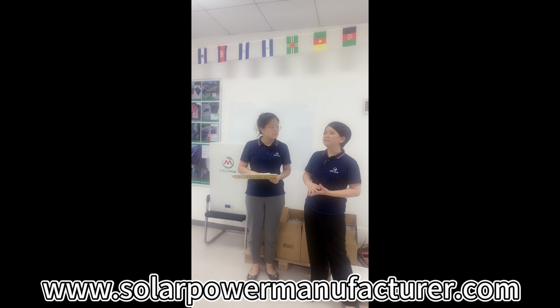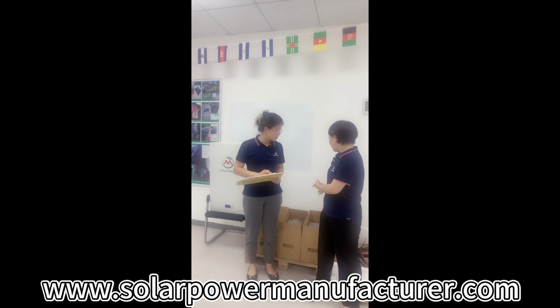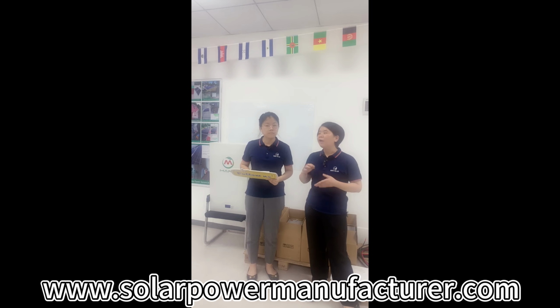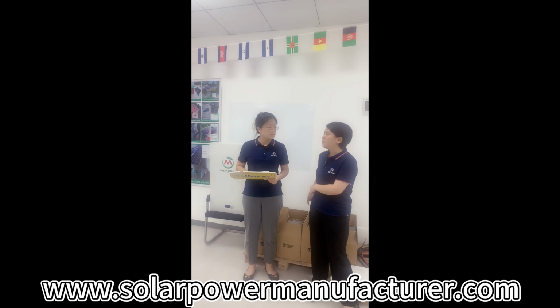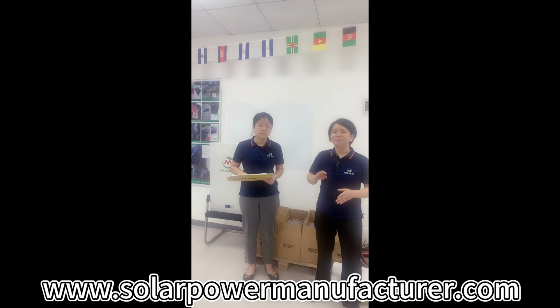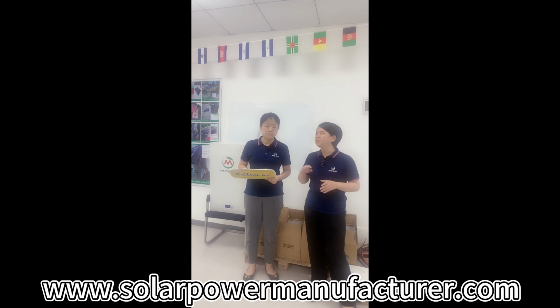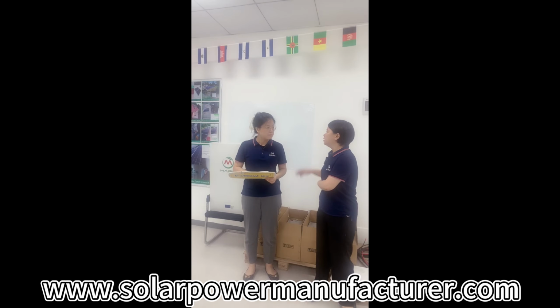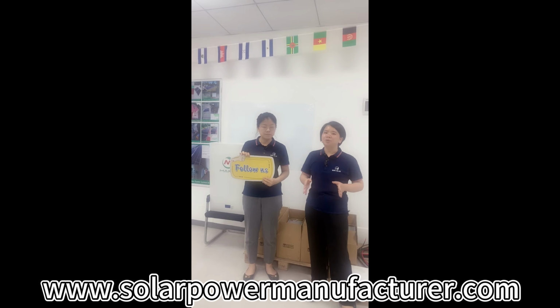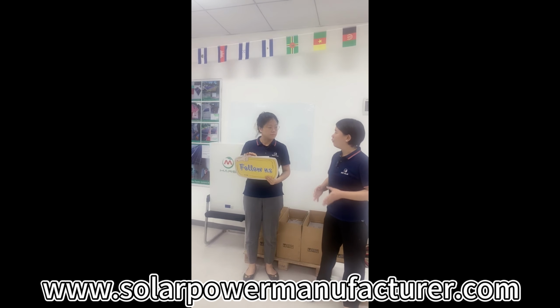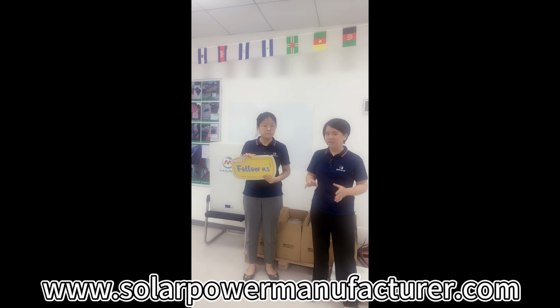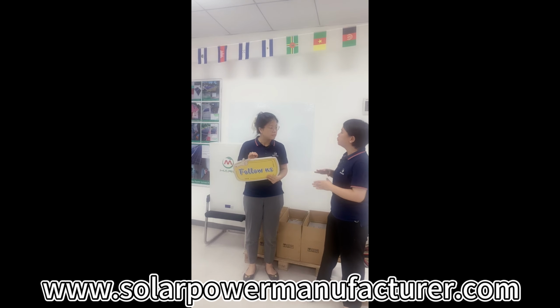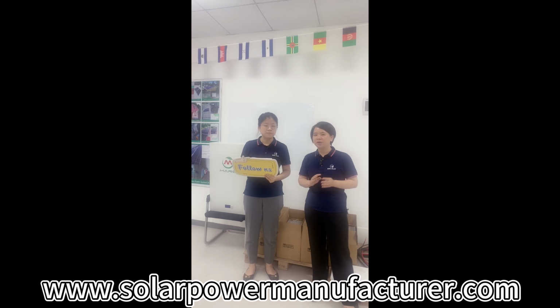It means that with the same capacity, the gel batteries, the capacity is 10 kilowatt hours for these 4 pieces, so you can use 7 kilowatt hours of power from these gel batteries. And with the same capacity, the lithium battery will provide 10 kilowatt hours of power you can use. That's the first difference for these two types of batteries, so the DOD will be different.